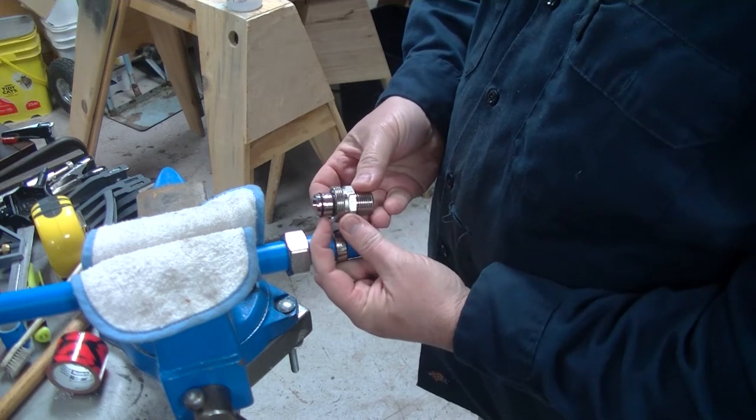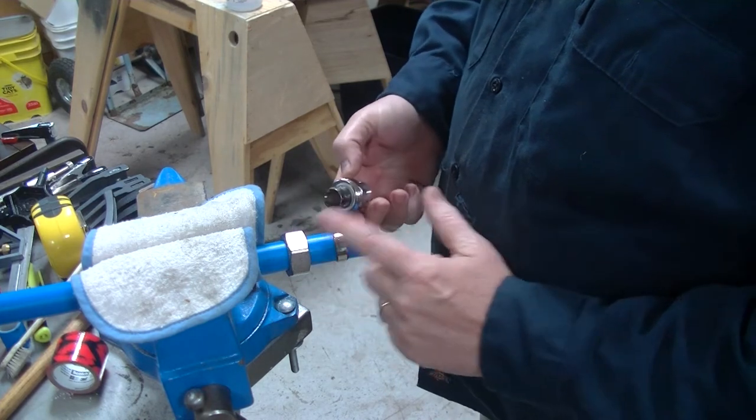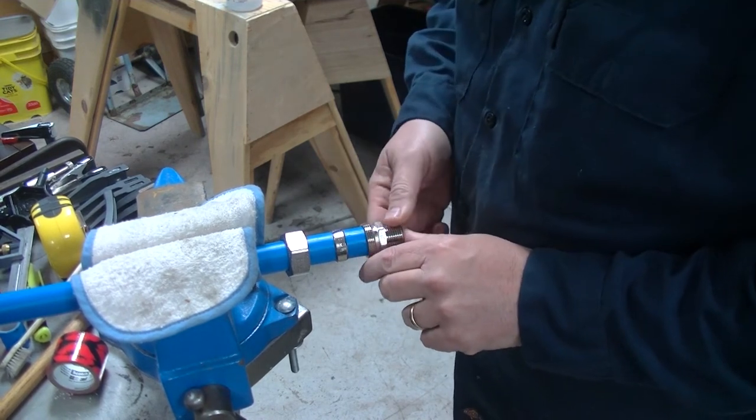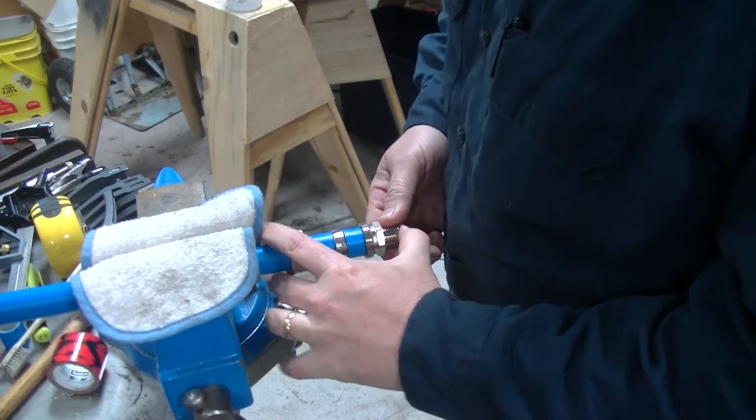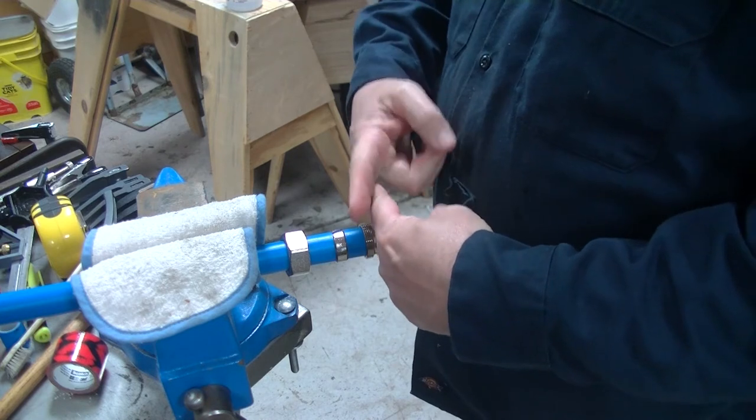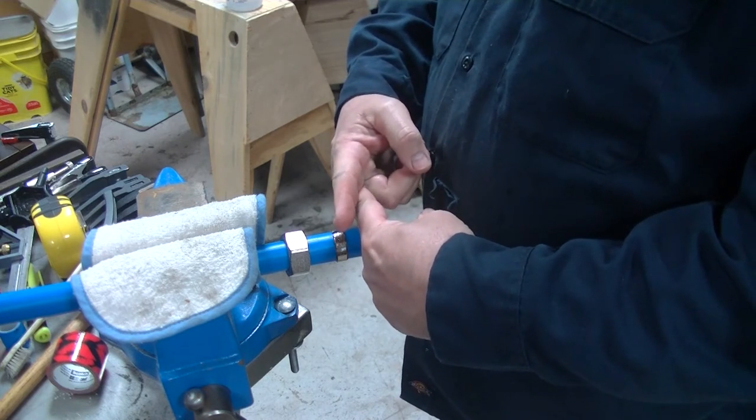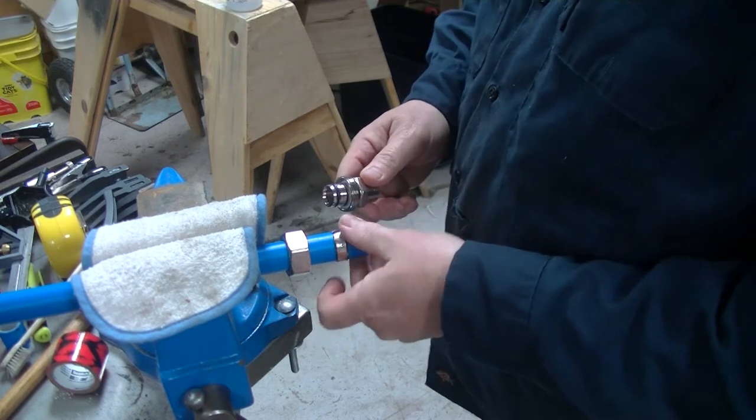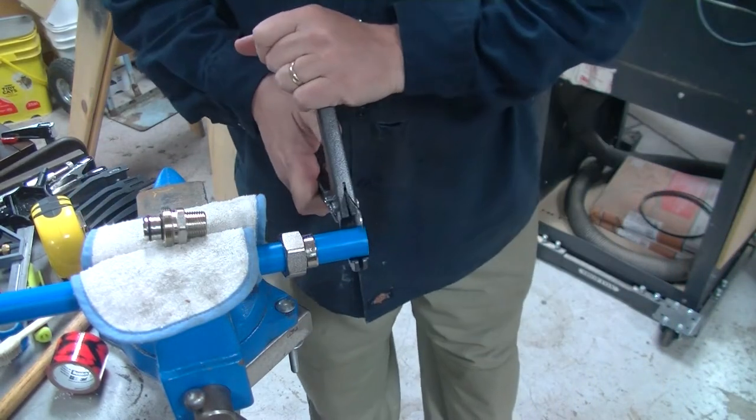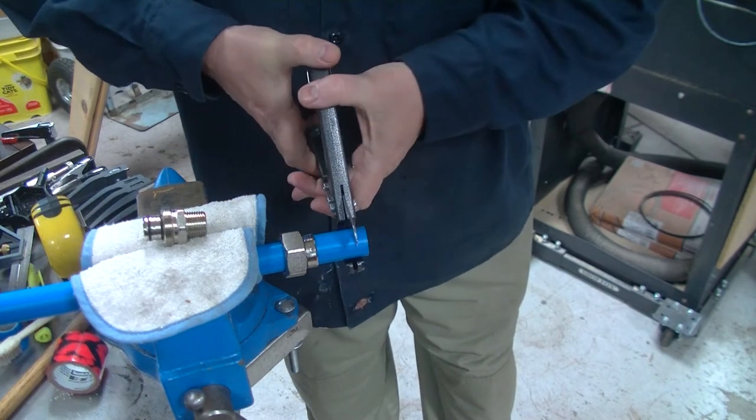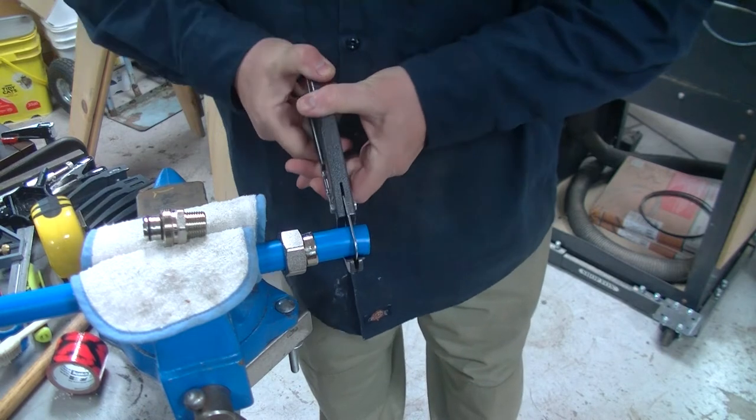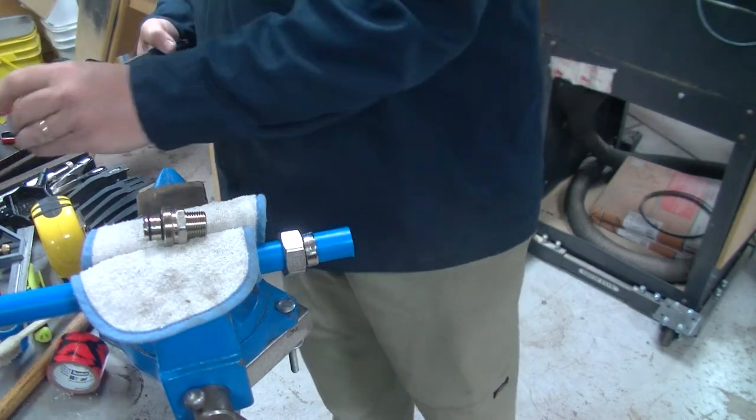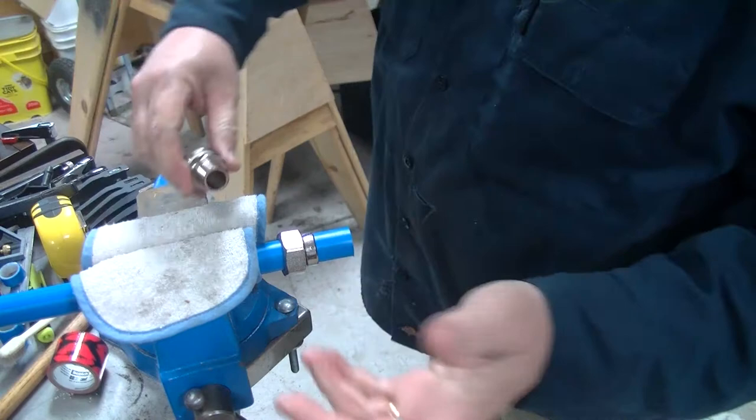I'm going to slip this compression nut. Then there's a compression ring or compression clip. There is a white seal on the inside here. And we've got two O-rings and a couple of barbs. So when we crunch this down, this is not going to want to spit it out. Now, the problem is, with this not being 90 degrees, when I push this on here, here's my mating surface like this. The end of my tube is like that. It's not like this. So I don't have a complete seal around the top of that. So I need to go in and I need to recut that.